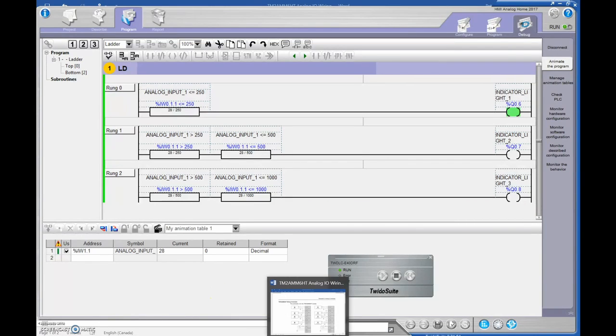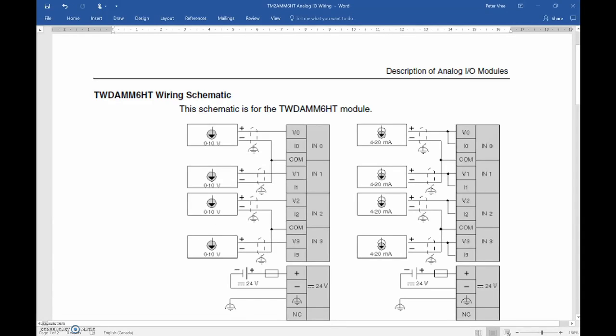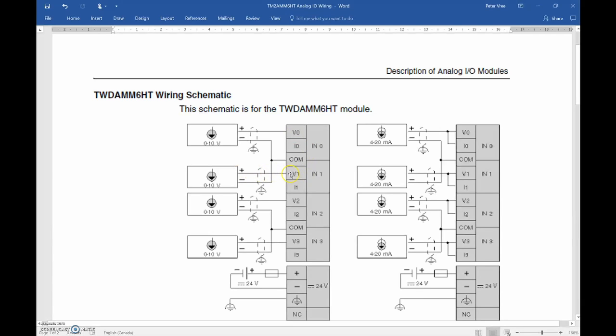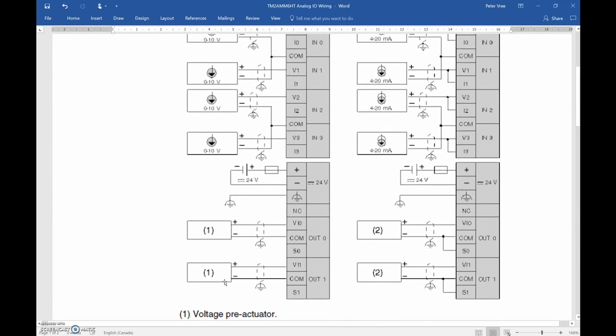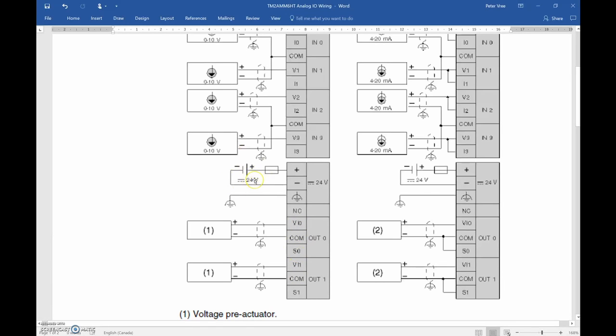So if I go here to my Word document, this is the wiring that I was going off of for the analog card. So you can see here that I'm using my first input here, or I guess the second one, but V1, right? So I need to have the positive signal going into V1. So I have a sourcing input. The negative is going to the common. And I had that set up, but below here, you see this 24 volts? I didn't provide that analog card with that 24 volts DC. I was under the impression that that 24 volts DC was only required if I was having these outputs turn on and having that output go out. So I thought this was the source for just the output, but this is the source for the entire card.